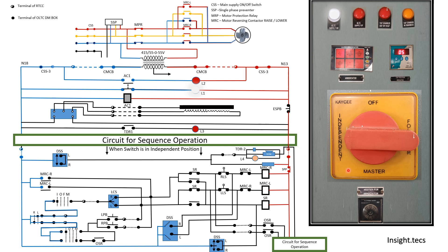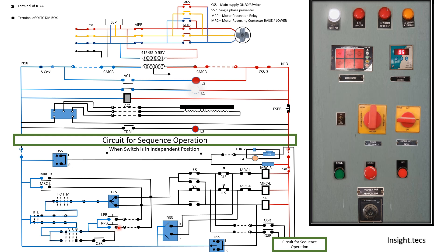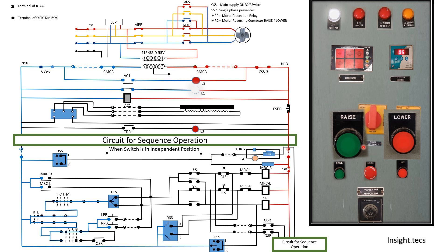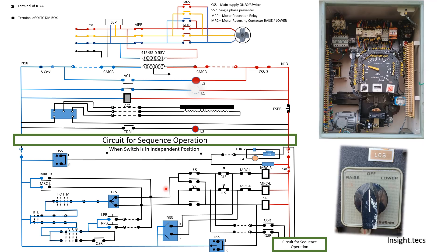In both cases — local or remote — the power moves to the sequence selector switch, which indicates either independent, master, or follower. Choosing independent mode, the power moves further. If operating in remote mode through the RTCC panel, there are two push buttons — raise and lower. Push the green button to raise and the red button to lower. In the DM box, the LCS switch also provides raise or lower selection locally.